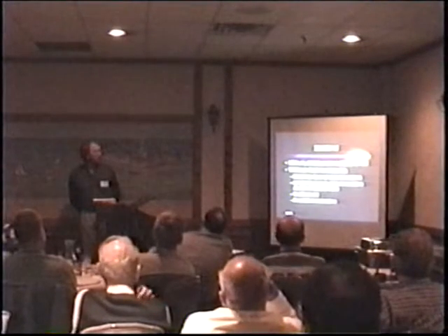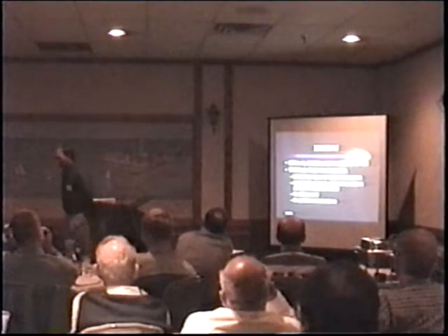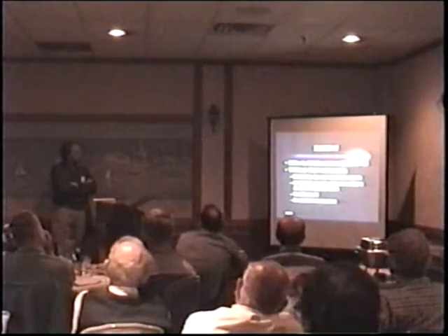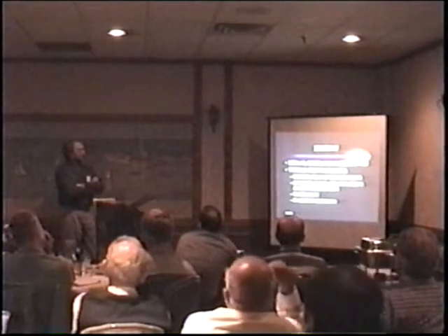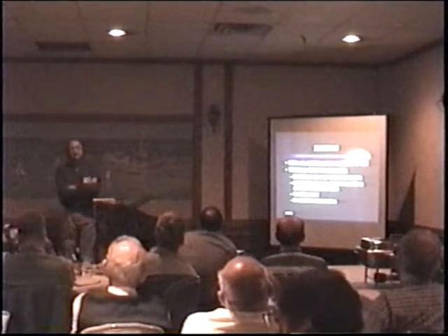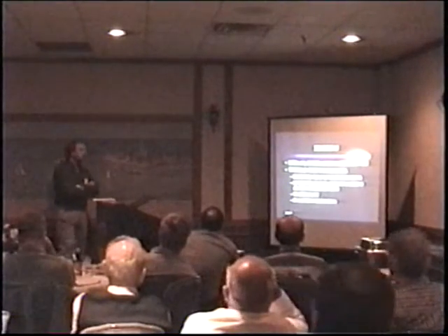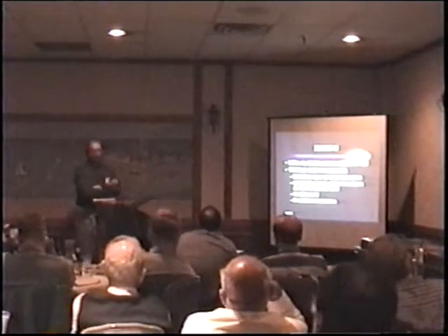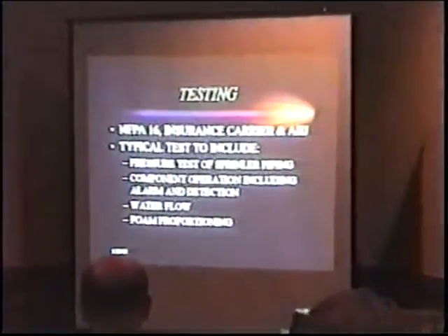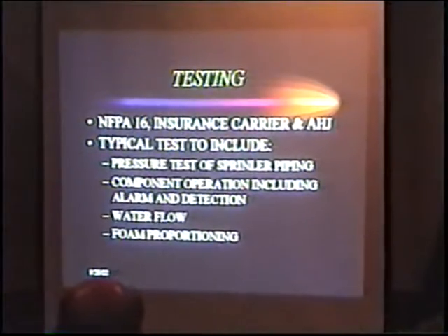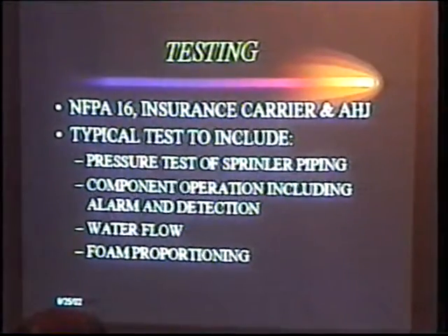Testing. I used to do a lot of testing when I first got started with Aero back in the 80s. You're going to be following your NFPA 16 guidelines. Your insurance carrier is going to have a lot of influence on how you test that system. And of course, your local authority is going to want to see some things too. And that's going to vary from site to site because each one wants to see something a little different. Typical test.